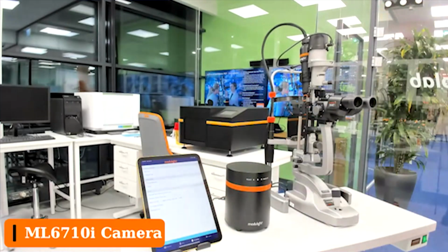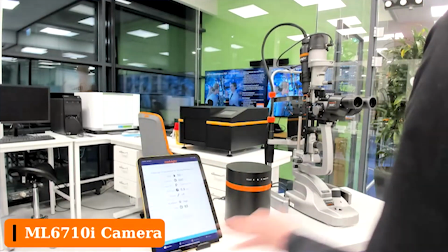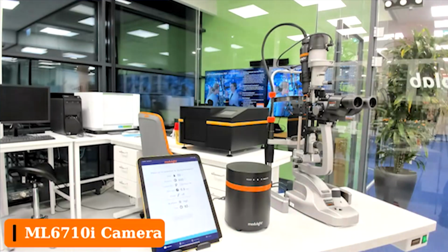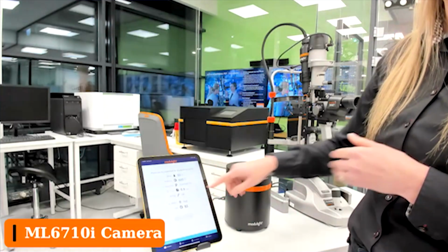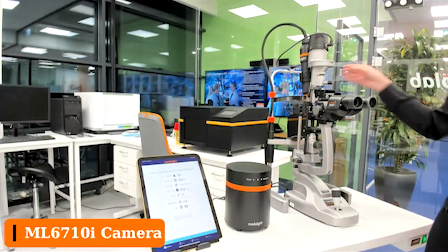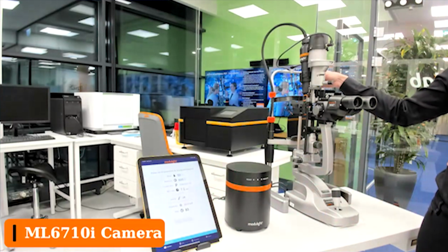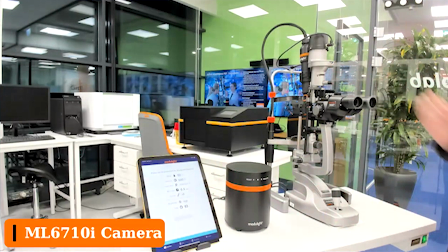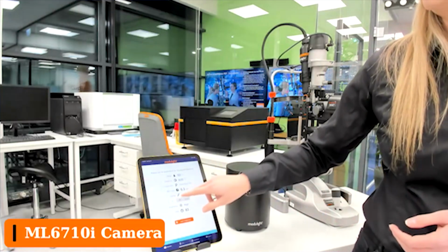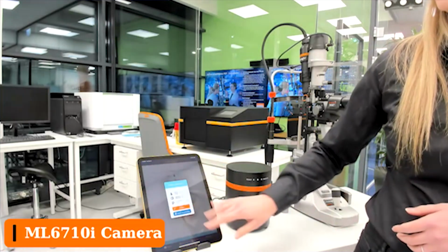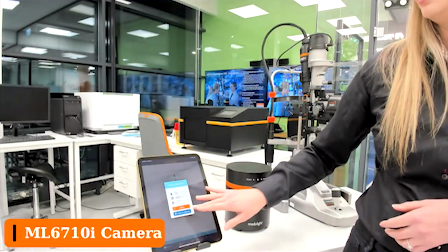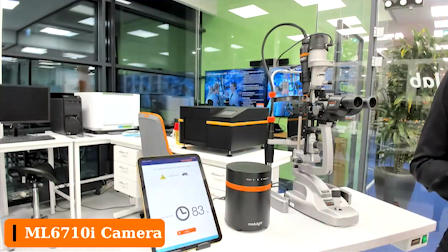Once you log into the application, you'll see this planning screen right here where the user can set the specific dose and the irradiance as well as their desired contact lens, which they wish to use for the treatment. The spot size itself is adjusted on the beam shaping unit right here. Once you're satisfied with these specific parameters, you'll simply press Start Treatment, confirm the parameters, and start the treatment by pressing the foot pedal.